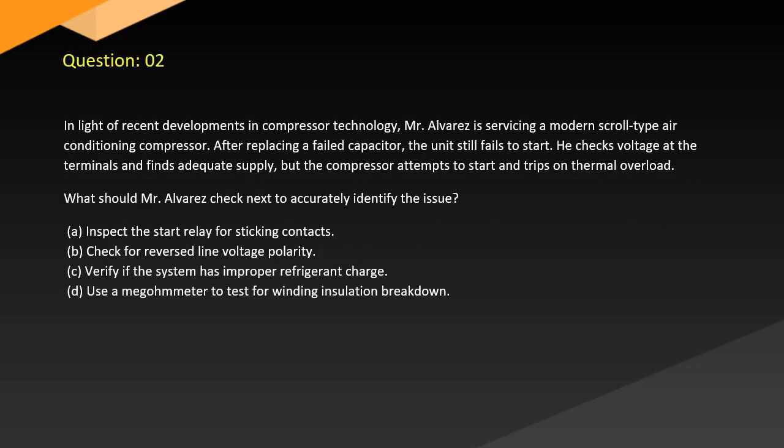Question 2. In light of recent developments in compressor technology, Mr. Alvarez is servicing a modern scroll-type air conditioning compressor. After replacing a failed capacitor, the unit still fails to start. He checks voltage at the terminals and finds adequate supply, but the compressor attempts to start and trips on thermal overload. What should Mr. Alvarez check next to accurately identify the issue?